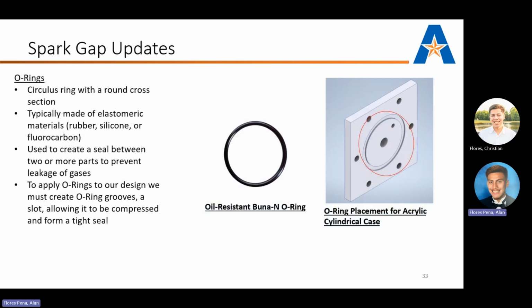So, some of the updates from the issues we saw in the previous two designs: we wanted to incorporate O-rings, which are circular rings with a round cross section. Typically they're made of an elastomeric material such as rubber or silicone, but we chose an oil-resistant Buna O-ring for our design. It is used to create a seal between two or more parts to prevent leakage of gases. And to apply the O-rings to our design, we must create an O-ring groove, basically a slot, allowing it to be compressed and form a tight seal.